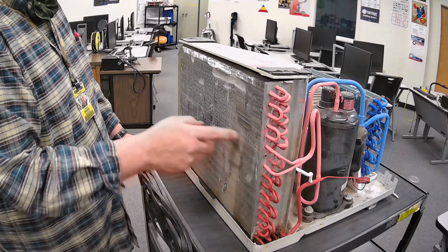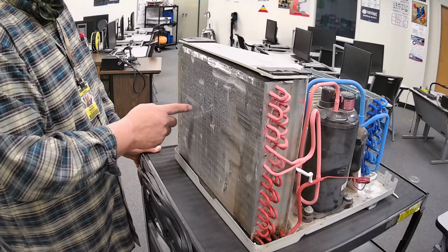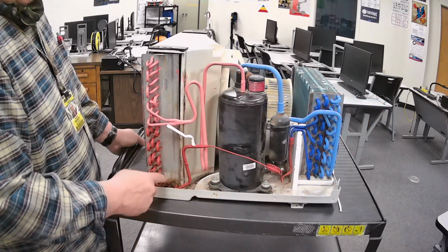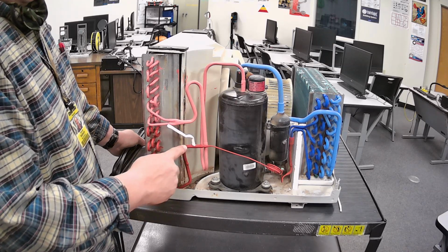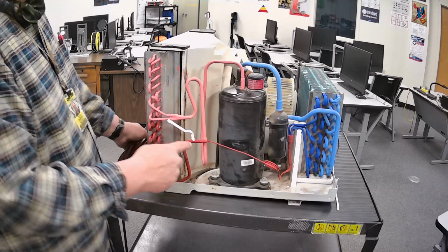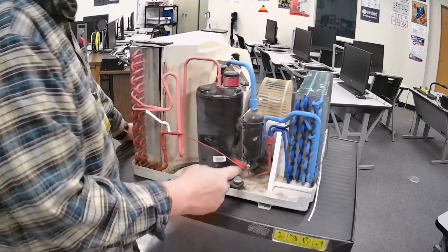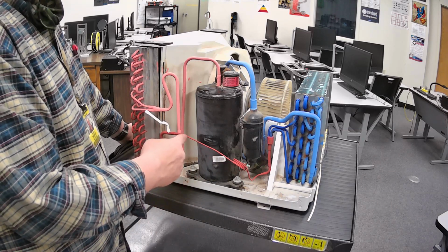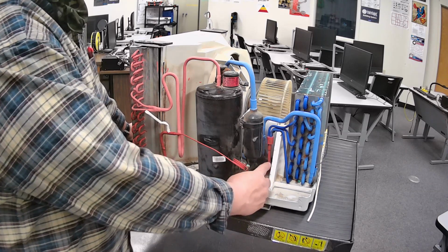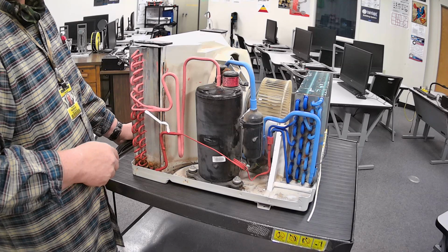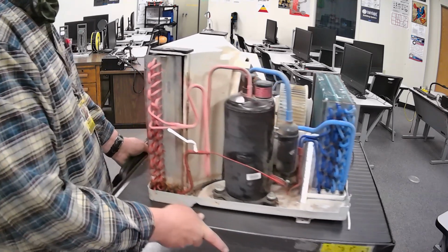It's like basically inside here it's starting to rain. As it cools, it becomes liquid again. And as it becomes liquid, before it comes out, it's nothing but liquid coming out of it. So now it's nothing but high pressure, high temperature liquid at this point. And again, as it goes from a liquid and goes through the meter device, the meter device reduces it from a high pressure, high temperature liquid, and turns it into a low pressure, low temperature liquid again. And then it starts the whole process over again. All right? That's the basic circuit.